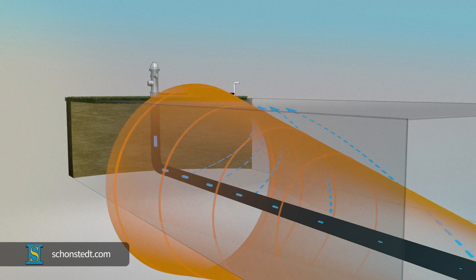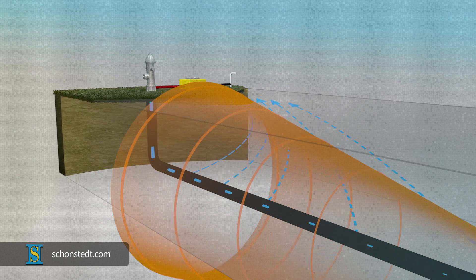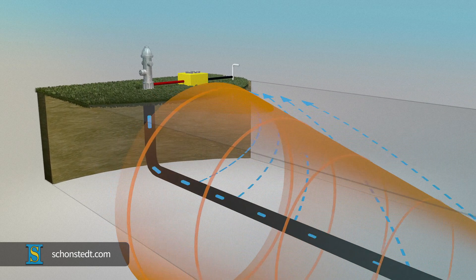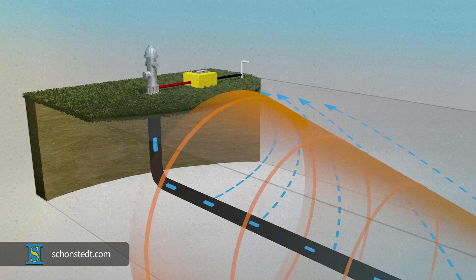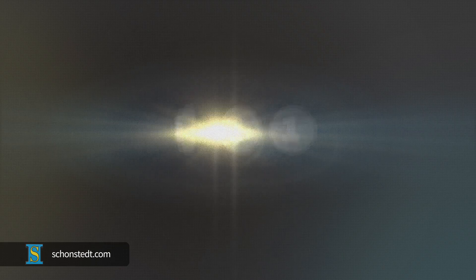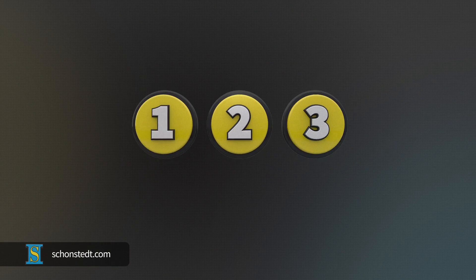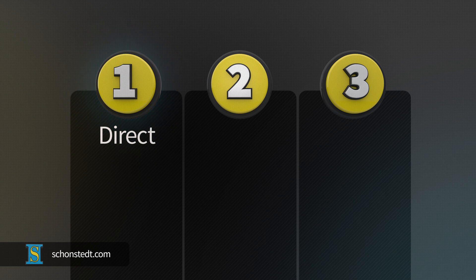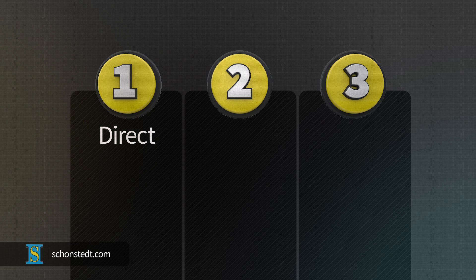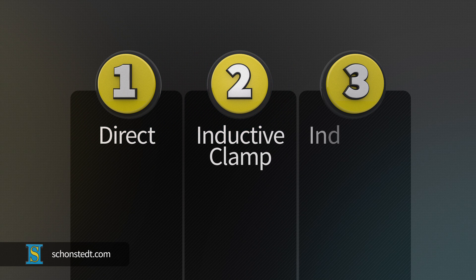Active locating requires you to create an electrical circuit through which current can flow. This can be accomplished with three different types of connections, known as active modes. The three active modes of connecting are direct, also known as conductive, inductive clamp, and inductive.